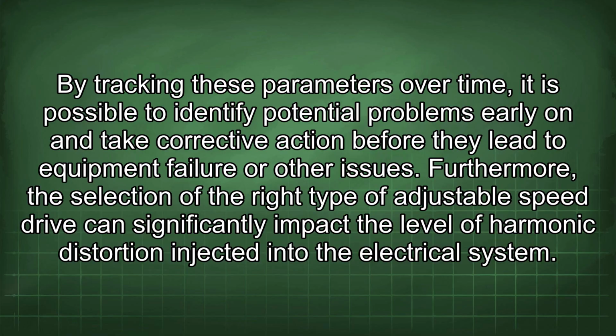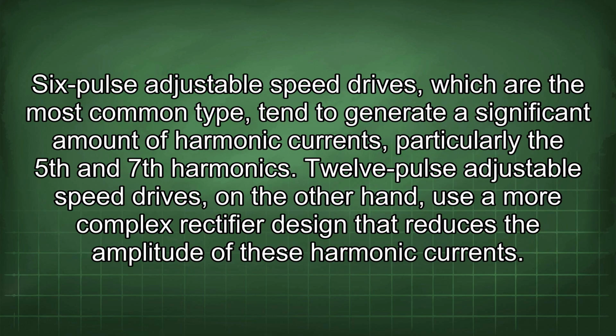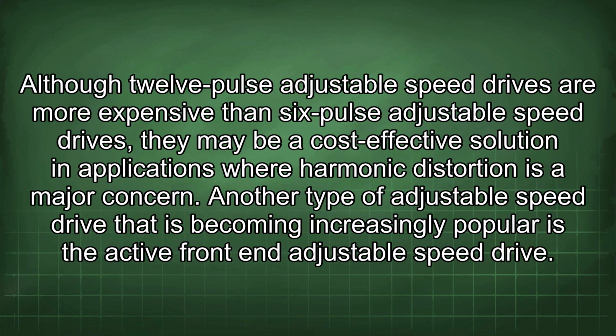Furthermore, the selection of the right type of adjustable speed drive can significantly impact the level of harmonic distortion injected into the electrical system. 6-pulse adjustable speed drives, which are the most common type, tend to generate a significant amount of harmonic currents, particularly the 5th and 7th harmonics. 12-pulse adjustable speed drives, on the other hand, use a more complex rectifier design that reduces the amplitude of these harmonic currents. Although 12-pulse adjustable speed drives are more expensive than 6-pulse adjustable speed drives, they may be a cost-effective solution in applications where harmonic distortion is a major concern.